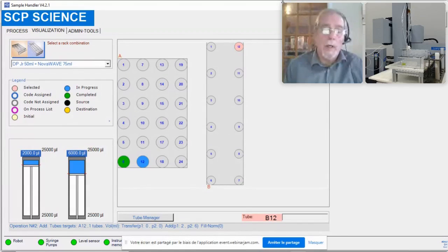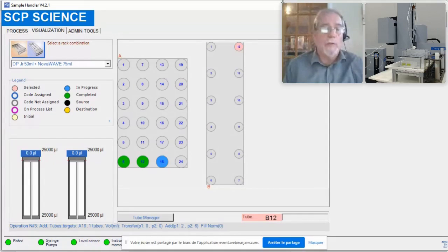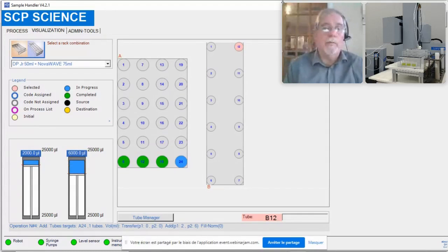So at the front end, this allows you to weigh your samples into your tubes, bring the rack to the system, pull up a program that can be saved to add the acids to the samples. So you can control how much acid is added to each one of the samples in real time. You can also control the numbering of the rack positions to duplicate your numbering system from, now you see that A1 is in the back left-hand corner. You can make 1 in either one of the 4 corners and count in that direction. So we've added acid to the 4 tubes that are at the front for visual effects here.